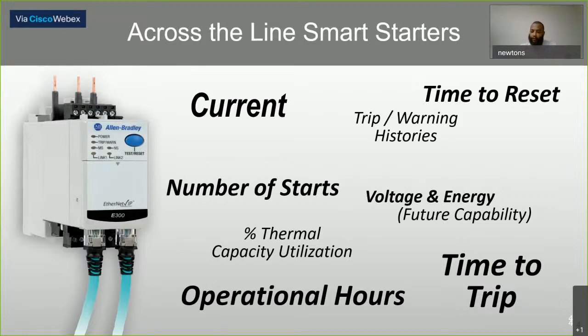This smart overload, which is what makes the across the line contactor smart or intelligent, is powerful because it comes with embedded Ethernet, with 2 Ethernet ports, which will allow you to set 1 IP address, and that allows you to send many diagnostics, much live real-time information to your integrated architecture system. Just like we mentioned in the slide before, over the network you can monitor your current, the number of starts that have been initiated, your thermal capacity utilization, how many hours you've been operating that machine, and so on.